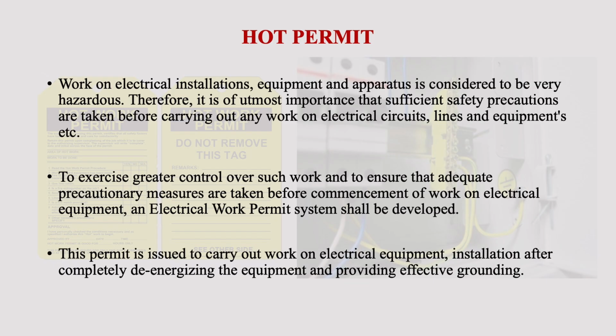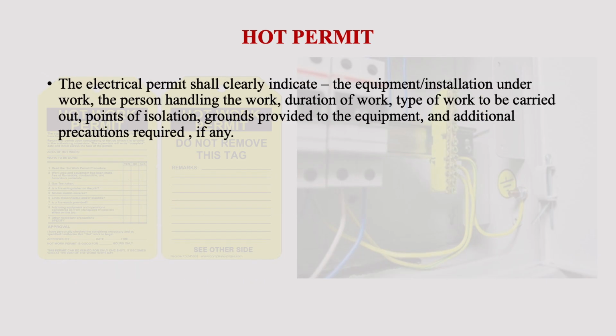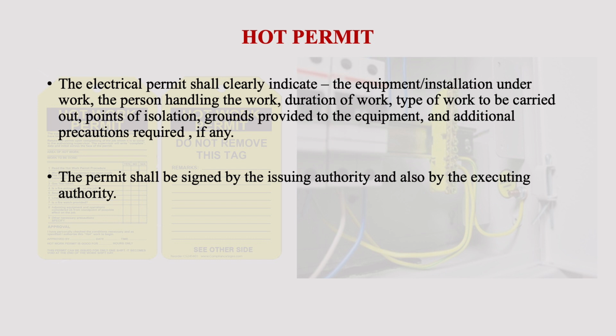The permit is issued to carry out work on electrical equipment installation after completely de-energizing the equipment from electrical energy and providing electrical grounding. The electrical permit shall clearly indicate the equipment or installation under work, the person who is handling the work, duration of the work, type of the work that is to be carried out, points of isolation, grounds provided to the equipment and additional precautions required if any. The permit shall be signed by the issuing authority and also by the executing authority. All work shall be carried out under supervision of a competent supervisor.